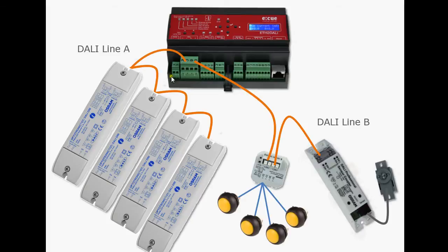All four ballasts are connected to DALI line A of the Ethernet to DALI. All input devices are connected to line B. Of course, you can have ballasts and input devices in one DALI line. One comment regarding light sensors: they are not defined in the current DALI standard. For this reason only OSRAM sensors are supported. And as they require constant polling, you should not have too many of them in one DALI line — let's say a maximum of eight.